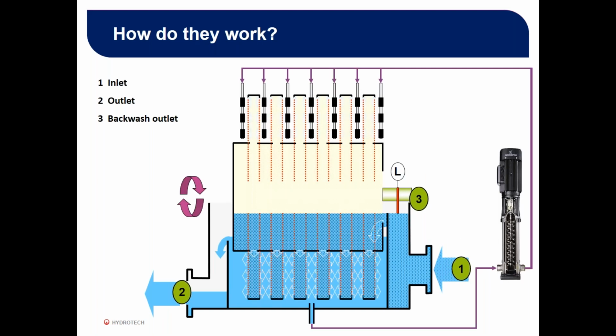The backwash is taken from the effluent tank in its own unit, put through the backwash pump, through the backwash spray nozzles that you see at the top. This is happening while the discs are rotating, and it's kind of difficult to see in this two-dimensional image, but these discs, the dirty ones that have the solids built up, are being rotated out of the water, and clean discs are being rotated into the water. As this rotation is happening, the dirty discs are being sprayed clean from the backwash nozzles. When the backwash nozzles spray the solids off of the filter cloth, they're collected in a trough within the disc filter, and the sludge flows out by gravity. So in by gravity, out by gravity, and the sludge also flows out by gravity.